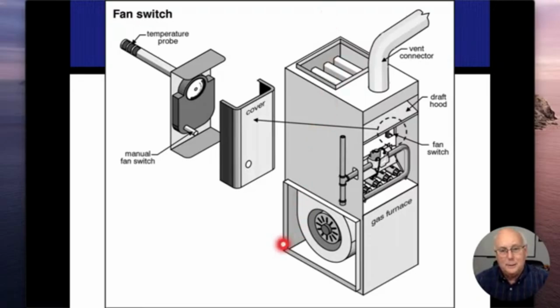So when I'm talking about a 30 to 60 degree temperature rise, if we come in here at 70, this is where my heat exchanger is going to be. That's where I'm going to add heat to it. And then above the heat exchanger and my plenum, that's where I want to be at that 100 to 130 degree mark. All right. Now, if this blower fan fails, and because that fire is going to be lit, that fire is going to be constantly adding BTUs to the metal of the heat exchanger. So it's going to keep getting hotter and hotter and hotter. This furnace is engineered so that as many BTUs as I'm adding through the fire here, I'm going to be removing those BTUs with the blower fan that I'm circulating air through the house.